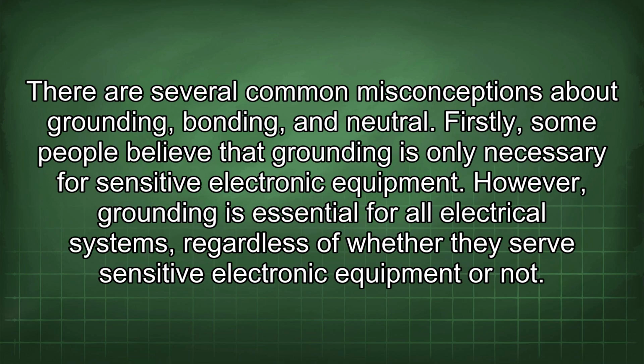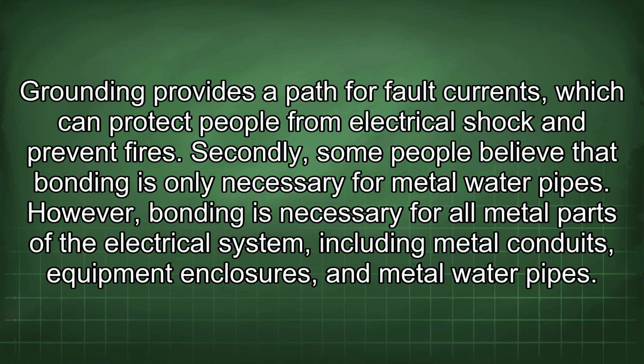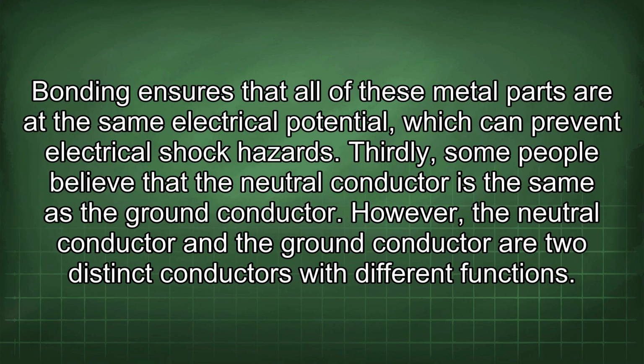There are several common misconceptions about grounding, bonding, and neutral. Firstly, some people believe that grounding is only necessary for sensitive electronic equipment. However, grounding is essential for all electrical systems, regardless of whether they serve sensitive electronic equipment or not. Grounding provides a path for fault currents which can protect people from electrical shock and prevent fires. Secondly, some people believe that bonding is only necessary for metal water pipes. However, bonding is necessary for all metal parts of the electrical system, including metal conduits, equipment enclosures, and metal water pipes. Bonding ensures that all of these metal parts are at the same electrical potential, which can prevent electrical shock hazards.